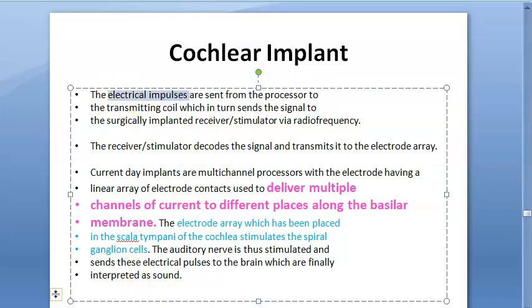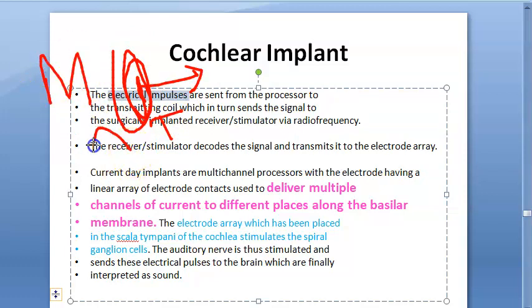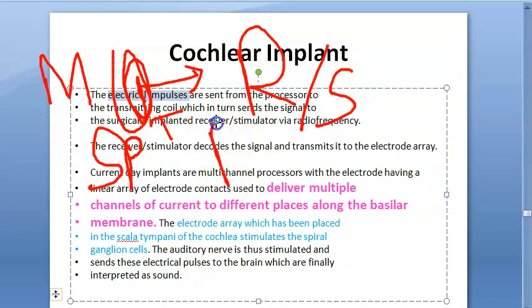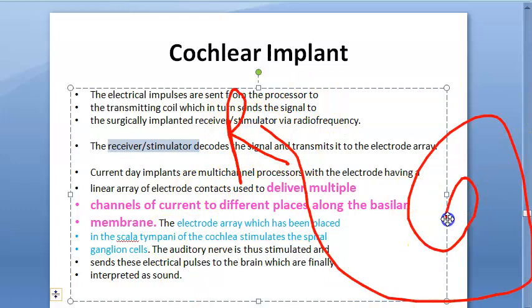After converting the sound into electrical energy, the electrical impulses go from the processor to the transmitting coil. The sound processor converts sound into electrical impulse, which is transmitted. You had a microphone which picked up the speech, then a speech processor converted it into electrical signal, then a transmitter sends the signal through the skin via radio frequency to the receiver or stimulator inside. The receiver decodes the signal and transmits it to the electrode array.